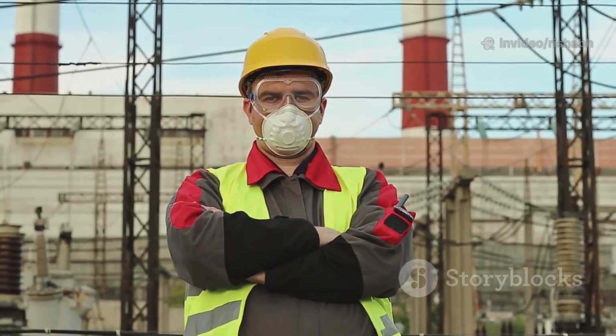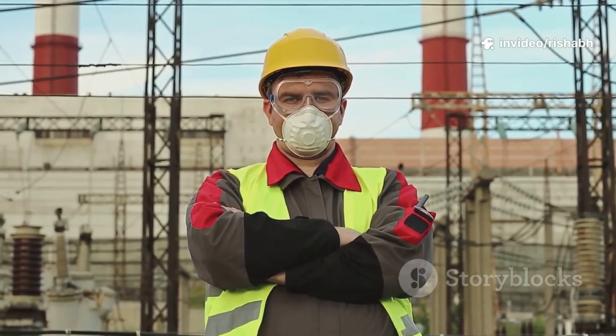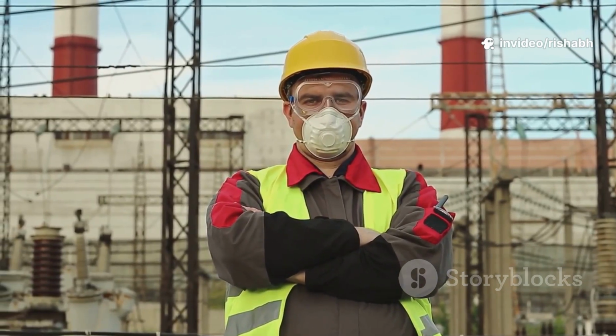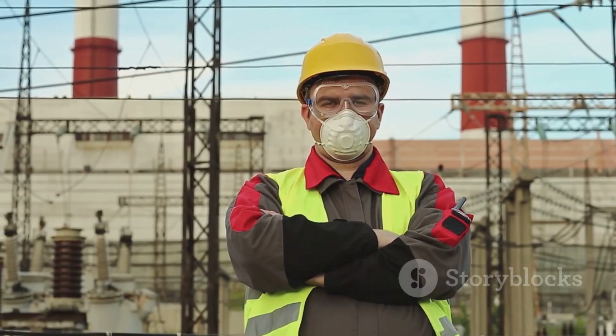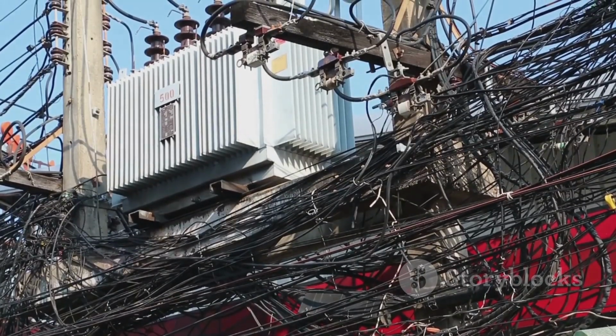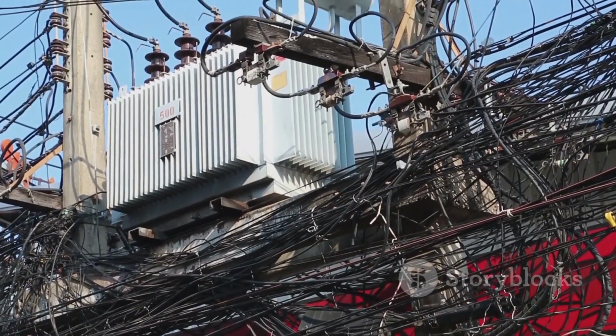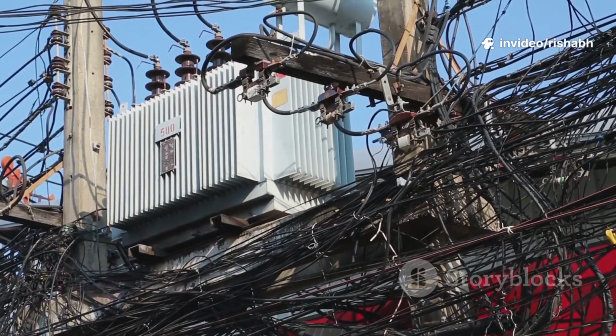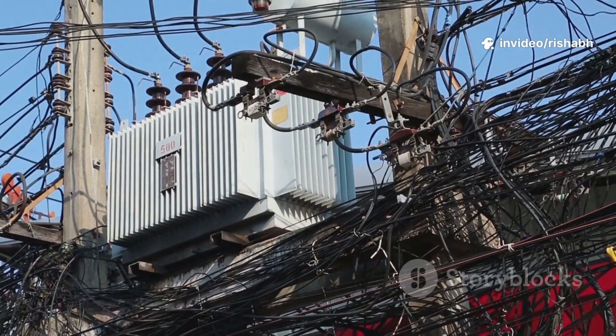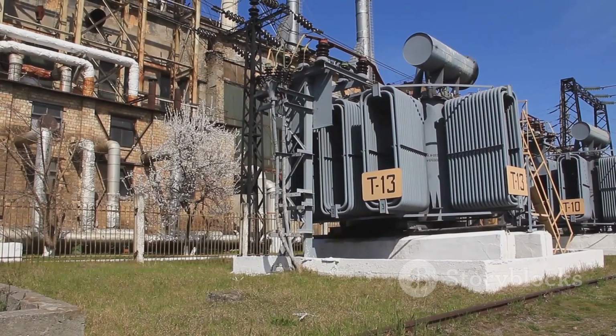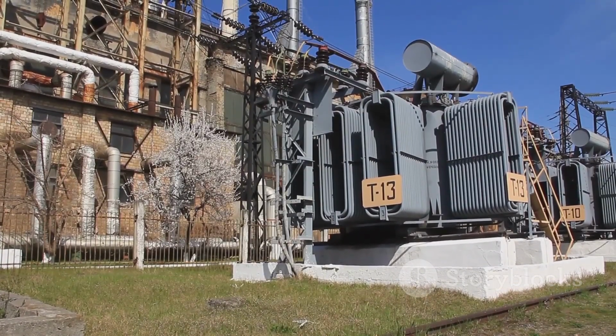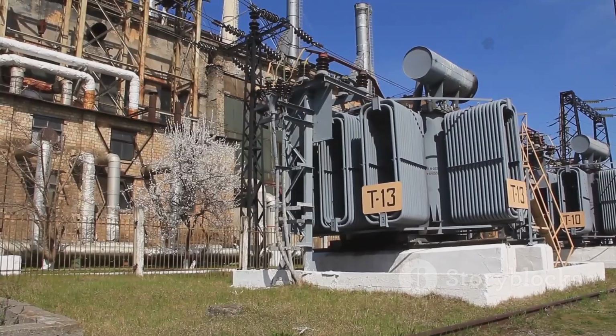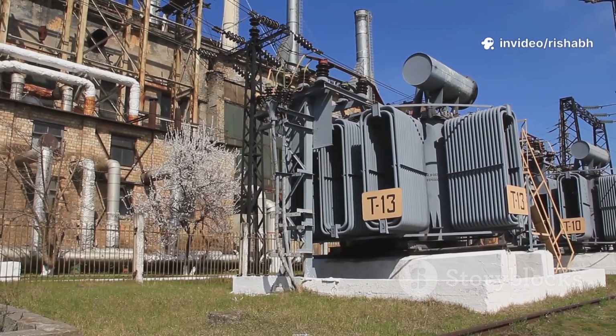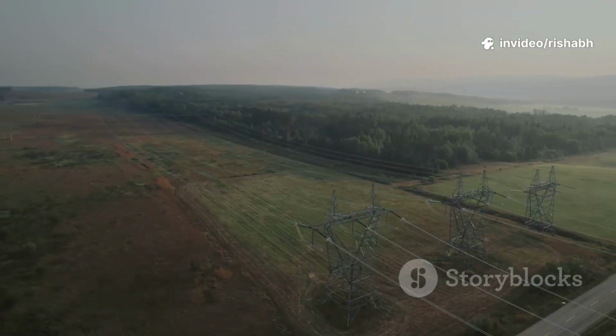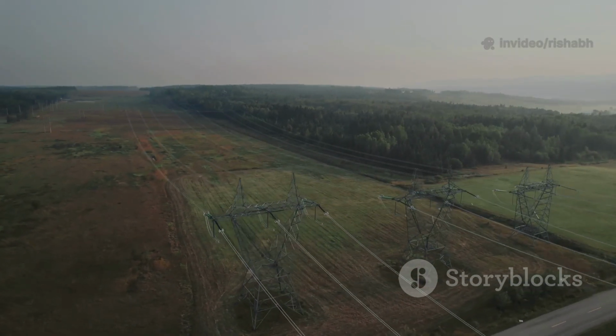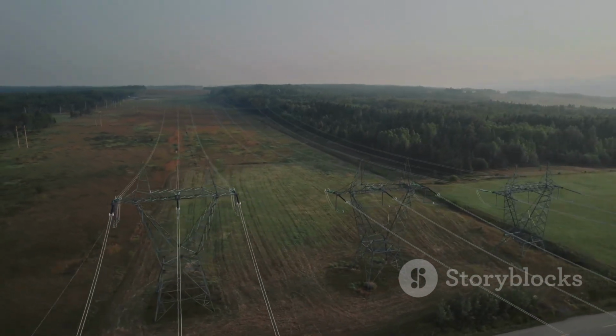Transformers perform their magic by changing voltage levels. Power is generated at a medium voltage, perhaps around 11 to 25 kilovolts. To send this power over hundreds of miles, we must minimize energy loss. The laws of physics tell us that loss is proportional to the square of the current. So, we use transformers to step up the voltage to extremely high levels, 220 kilovolts, 400 kilovolts, or even 765 kilovolts. This dramatically reduces the current, allowing electricity to travel vast distances with minimal waste.